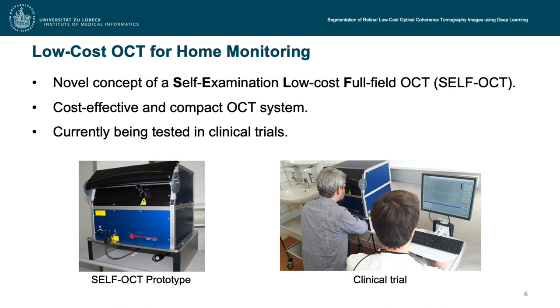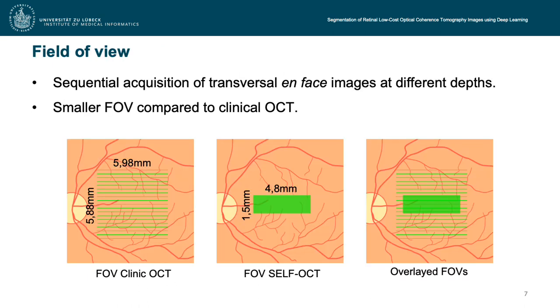Such a novel concept for a self-examination low-cost full-field OCT with the acronym SELF-OCT was developed by our colleagues at the Medical Laser Center. The SELF-OCT is a cost-effective and compact OCT device currently being tested in clinical trials. In contrast to established clinical OCTs such as the Heidelberg Spectralis, which produces non-adjacent cross-sectional images, the SELF-OCT acquires transversal en-face images at different depths, resulting in a densely sampled volume. Furthermore, the field of view of the SELF-OCT is much smaller than that of the Heidelberg Spectralis, but is sufficient to assess AMD.